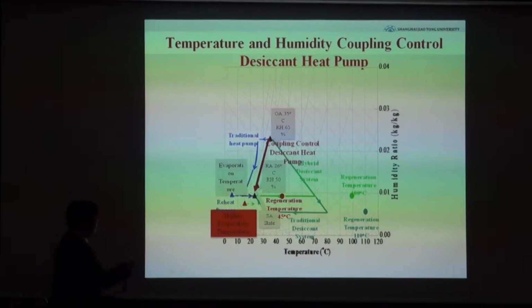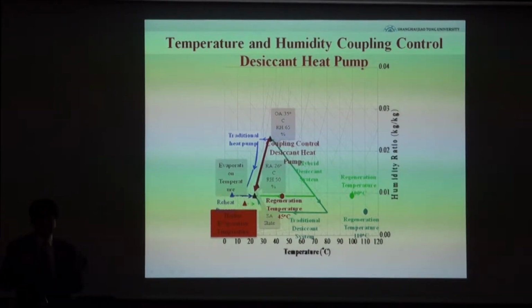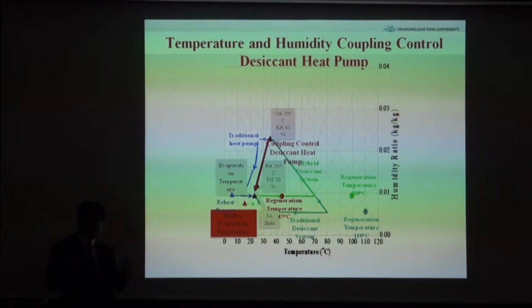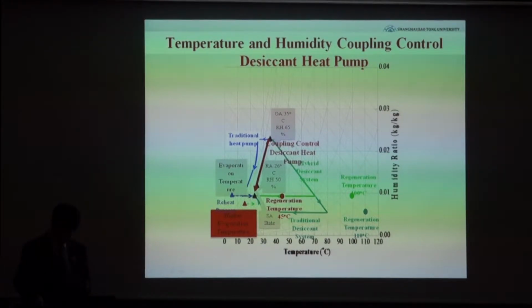This process means you need a very low evaporation temperature, so the efficiency is not good. But for air conditioning inside a room, we need 26 degrees centigrade. So in this case, it would be advisable, for a normal vapor compression system, to increase the evaporation temperature from 5 degrees centigrade to 15 degrees centigrade. That means dehumidification will not be possible, but the efficiency will be very high. So in this case, we need dehumidification by desiccant materials.